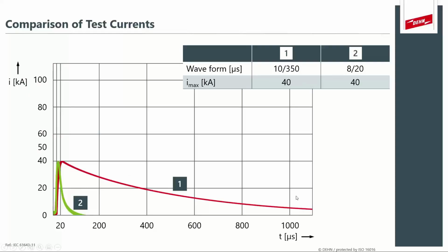So if we look at the curve, as explained previously, we peak at 10 microseconds, and we decay to 50% of the value, which is 20 kA, in 350 microseconds. Now, a surge is obviously a little bit quicker, but it decays much faster as well. So it reaches half of its value in 20 microseconds.